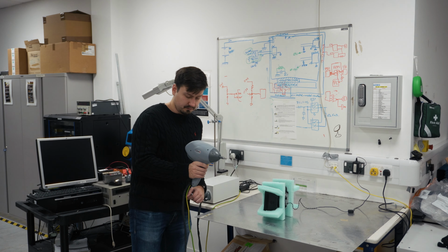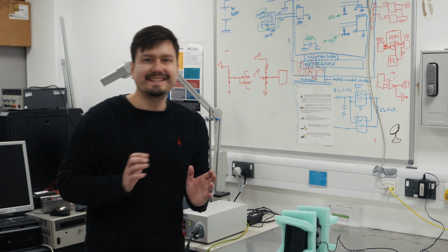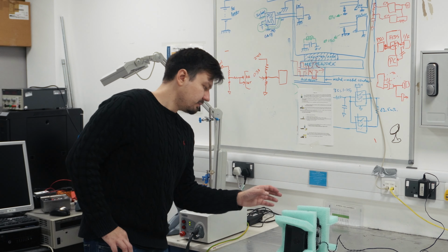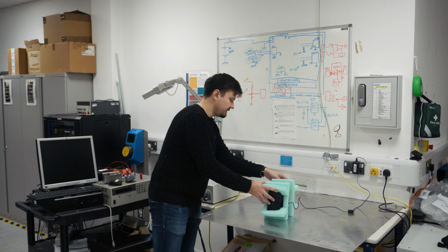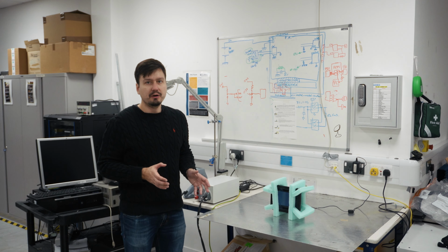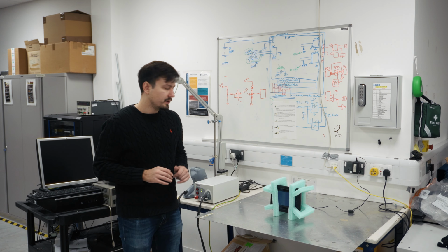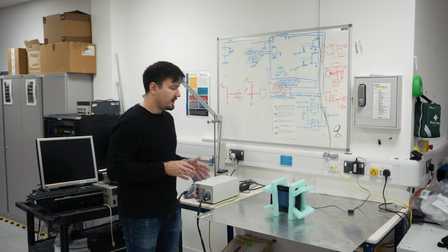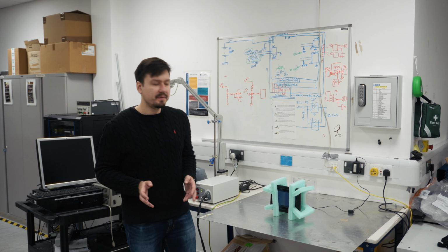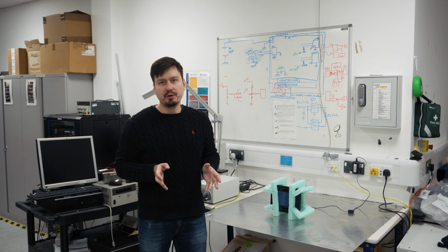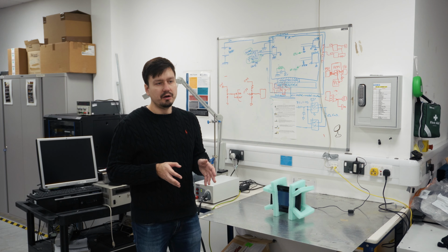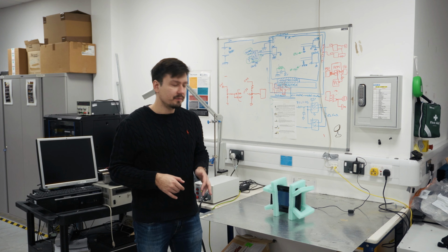So now if it restarts itself, I'm going to count it as performance criteria D. Sorry, I meant C. Yeah, you can see the device is back and it restarted itself without manual intervention, so that counts as performance criteria C. That means the test setup is working, and it is acceptable at 8 kilovolt to be performance criteria C, but not D.